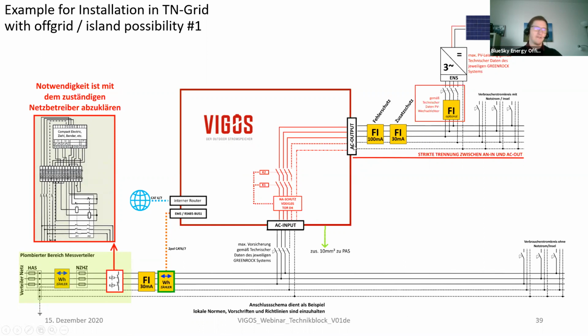The only thing is, if the grid failure comes at midnight and the battery is already completely empty at, for example, 4 a.m., the PV inverter has no microgrid where it can connect. So for that case, you would need a DC coupling PV, which is also black start capable. We will come to that in the slide after the next one.